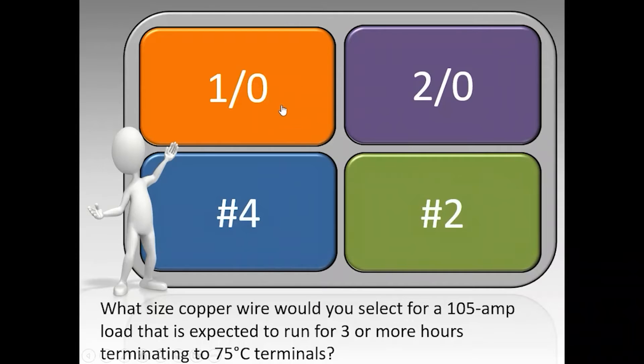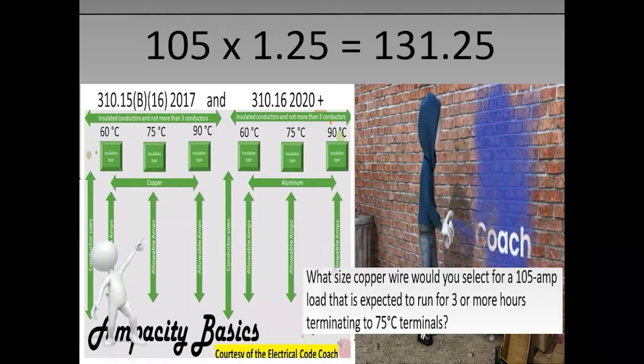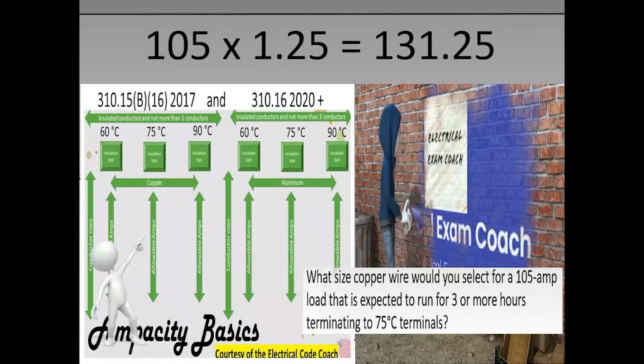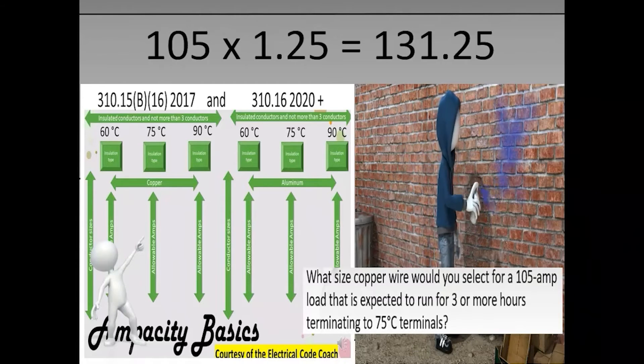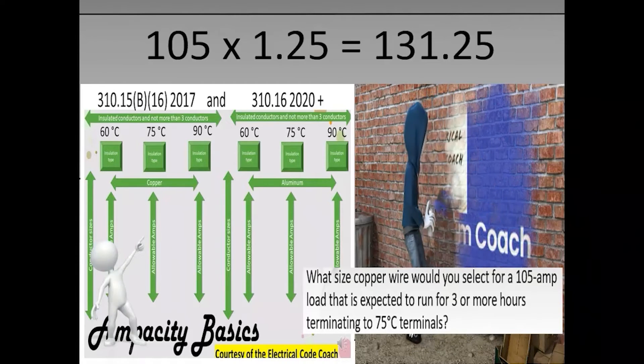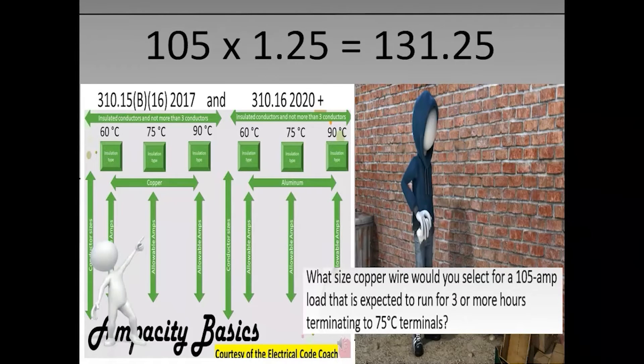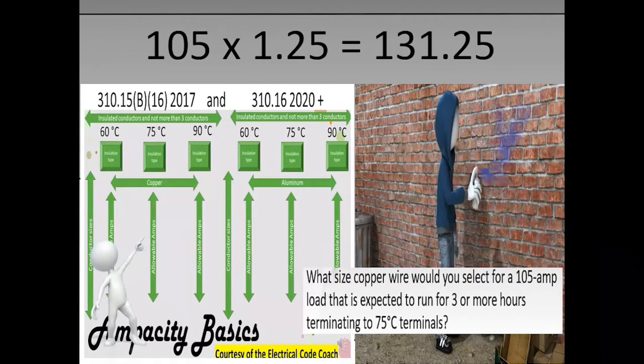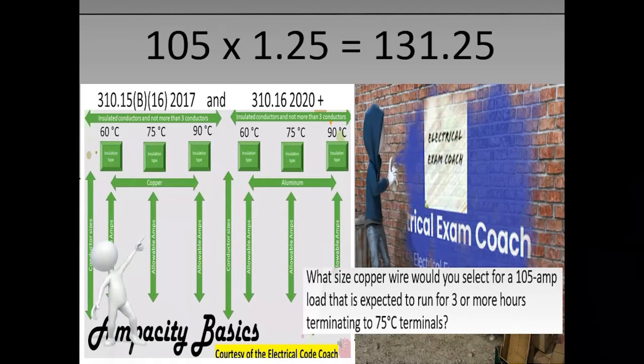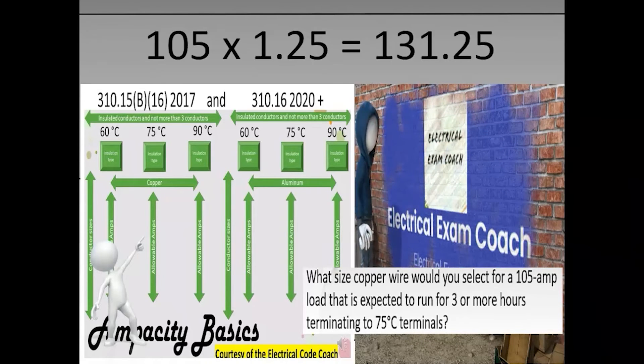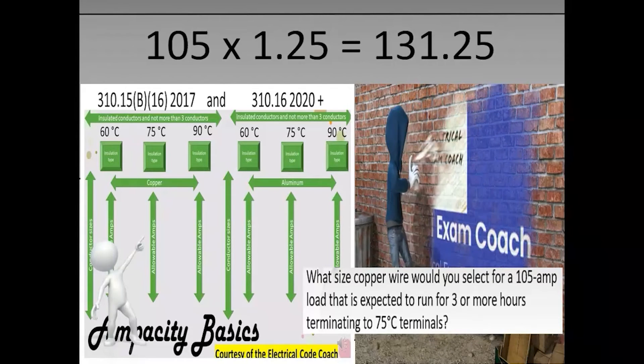The correct answer is 1-0. We take our starting ampacity and multiply it by 125%, giving a new known load of 131.25. We applied 125% because it's a continuous load. Then we head to our primary ampacity table and choose from the 75-degrees-C column, since it states we're terminating to 75-degrees-C terminals. We go down on the copper side to find a wire that covers our known load and select a 1-0.